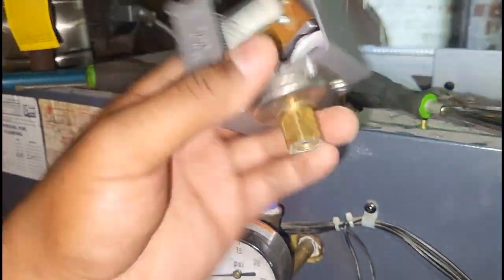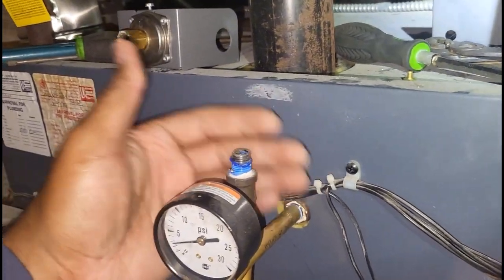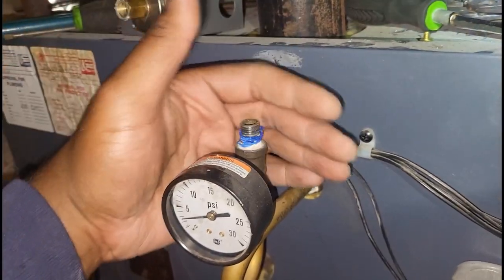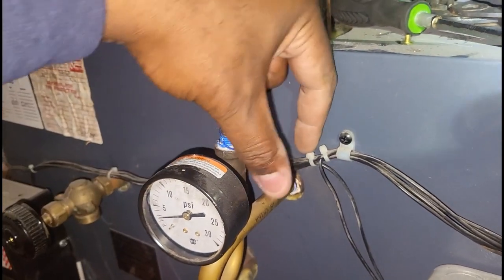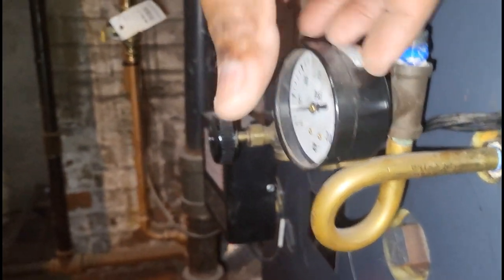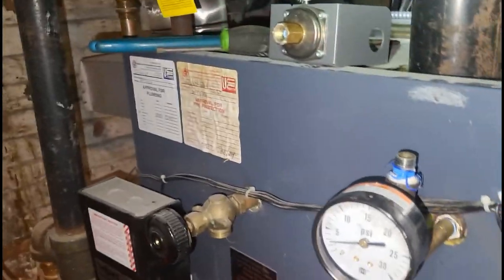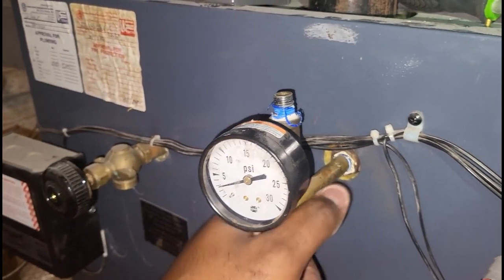The pressuretrol is off. The good thing about Weil-McLain steam boilers is they make their pressuretrols physically smaller, so it's a lot easier to remove them without breaking them. With those Crown pressuretrols you've seen in my previous videos, they're so big that even if you try to remove them they can snap because there's not enough space to service them. That's why with Crown pigtails you'll often see people add an extension nipple off the boiler to give enough clearance. Be careful when removing these — use a good pair of channel locks but don't go too crazy; you don't want to strip the threads or break the gauge.